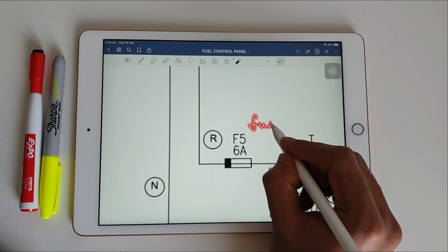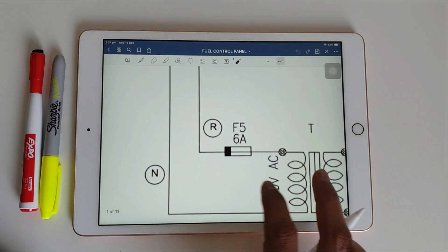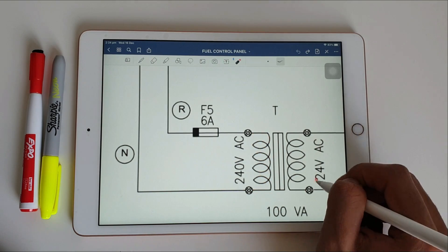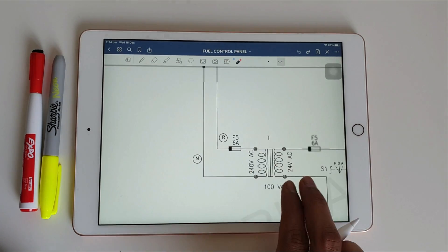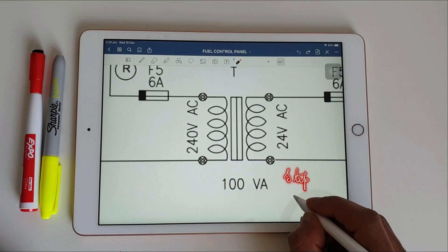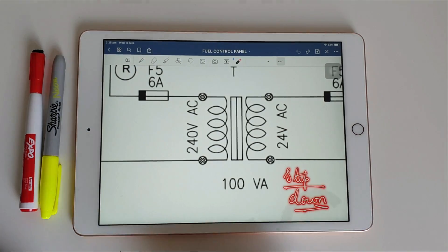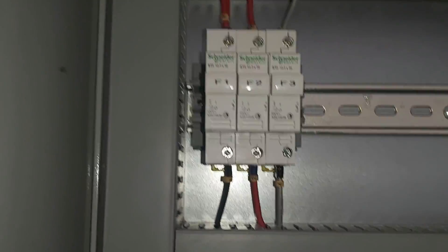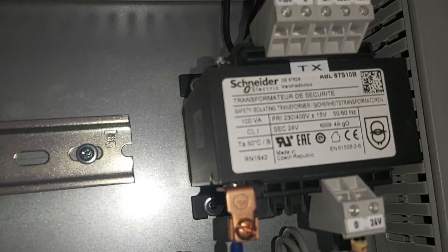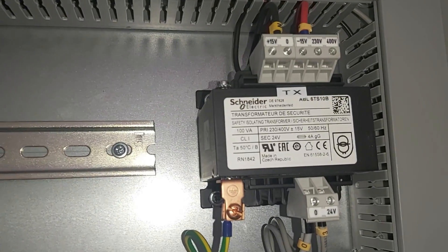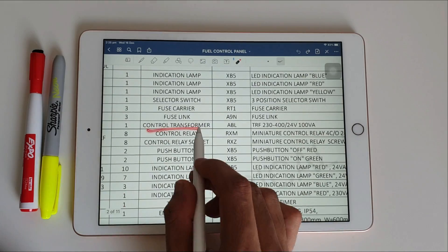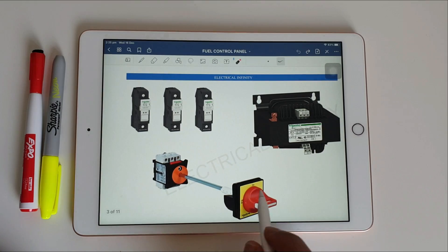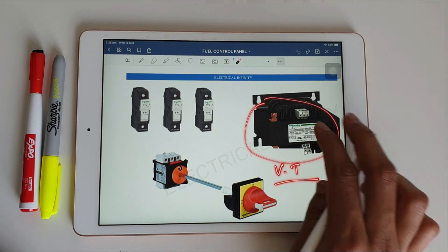From the emergency switch we are connecting again to one more 6 ampere fuse, and from this fuse we connect to a voltage transformer — a step-down control transformer from 240 volts AC primary to 24 volts AC secondary. This step-down transformer is rated at 100 volt-ampere. From this fuse we connect to the 240 volt terminal of the voltage transformer.